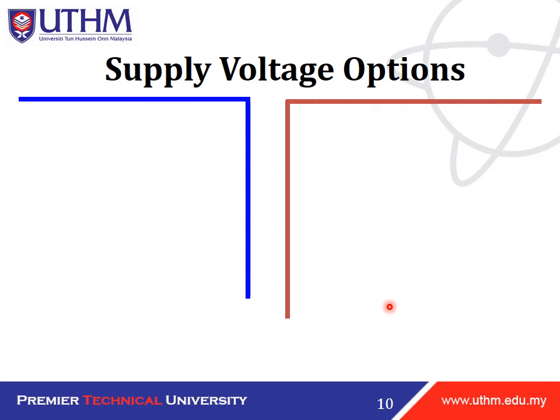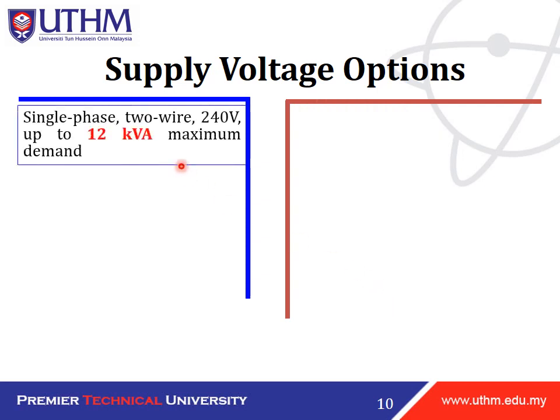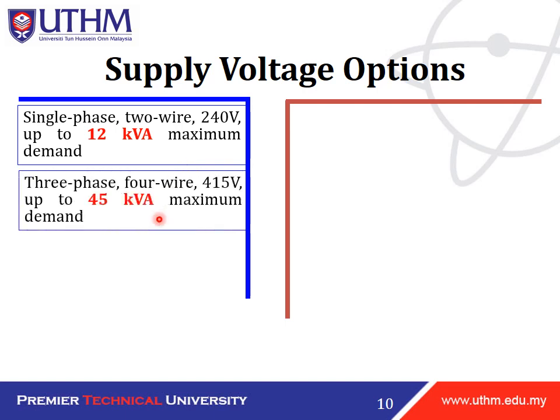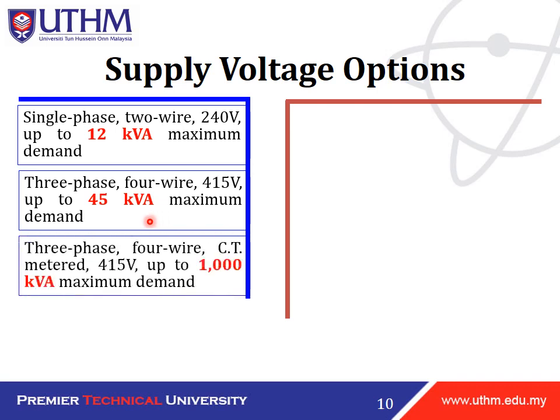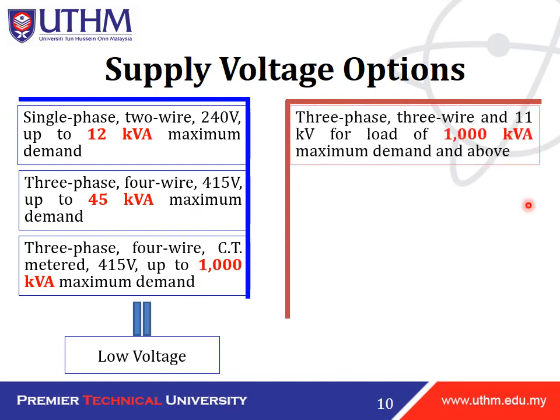As we have done before, we have two types of supply voltage options. So the first option has these characteristics: single phase two wire 240 volt up to 12 kVA maximum demand, and then three phase four wire 415 volt up to 45 kVA maximum demand, and then three phase four wire CT metered 415 volt up to 1000 kVA maximum demand. This is the characteristic of low voltage supply.